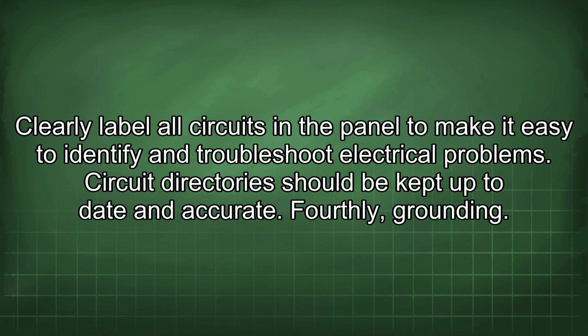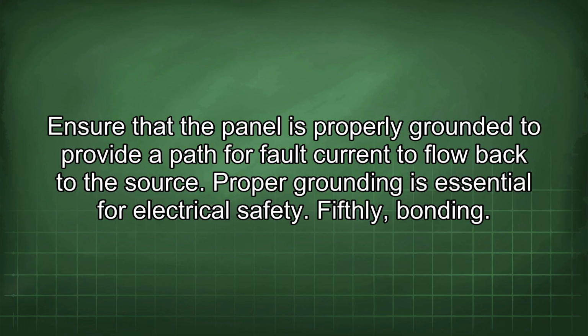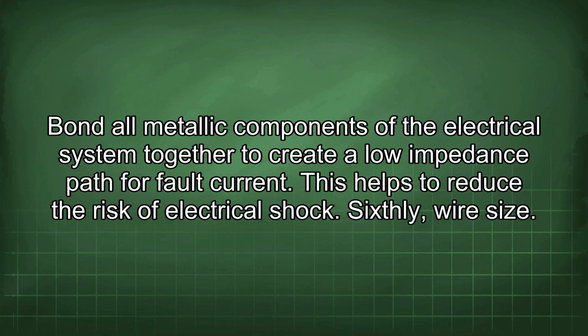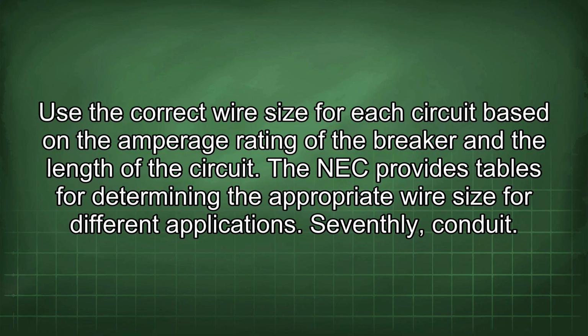Circuit directories should be kept up to date and accurate. Fourthly, grounding. Ensure that the panel is properly grounded to provide a path for fault current to flow back to the source. Proper grounding is essential for electrical safety. Fifthly, bonding. Bond all metallic components of the electrical system together to create a low impedance path for fault current. This helps to reduce the risk of electrical shock. Sixthly, wire size. Use the correct wire size for each circuit based on the amperage rating of the breaker and the length of the circuit. The NEC provides tables for determining the appropriate wire size for different applications.